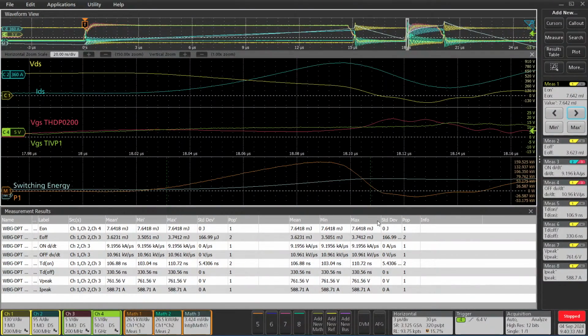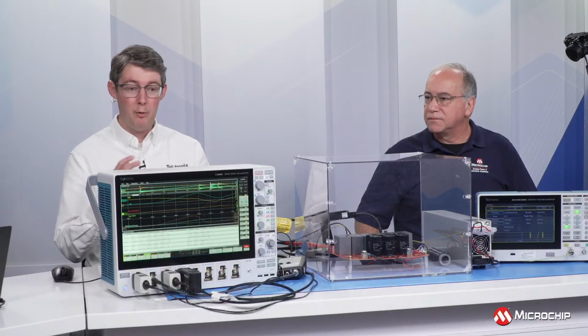The statistics on the right-hand side of the table - if we were to take multiple acquisitions and vary this board or module over temperature or time or different load conditions, these cumulative statistics would tell us how that change is occurring. So now we're getting both dynamic and static measurement characteristics of our device.